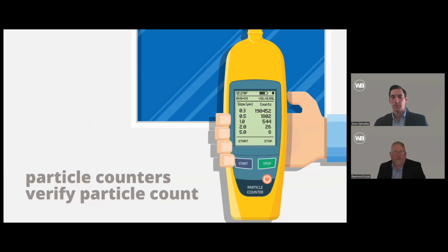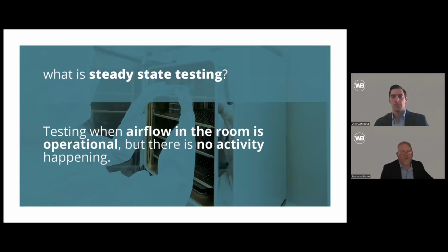One thing that's interesting is this idea of particle counters and being able to do a handheld one. We recommend everybody that runs a clean room has a handheld particle counter in there. Depending on what the science is, depending on the volume of the airflow that you need to run through the particle counter, they come in various sizes and qualities and calibration requirements. But it's important to make sure that you do understand when and why you need that particle counter and have the appropriate equipment to do so. If you outsource it or have it internal, either way it works.